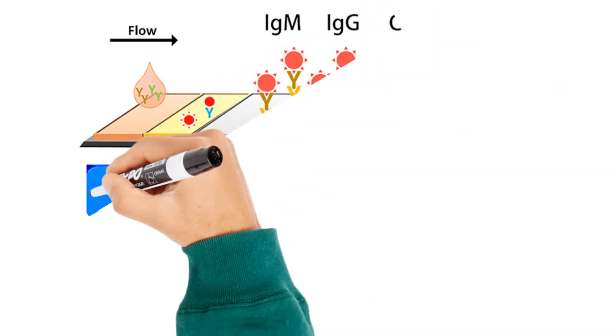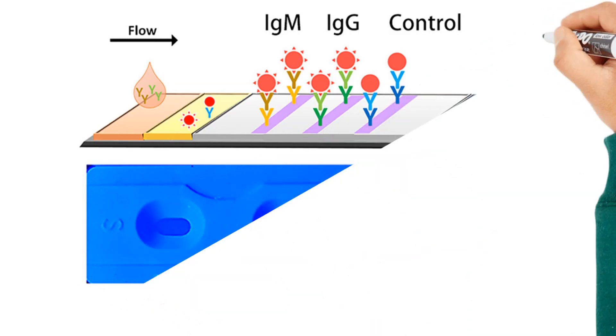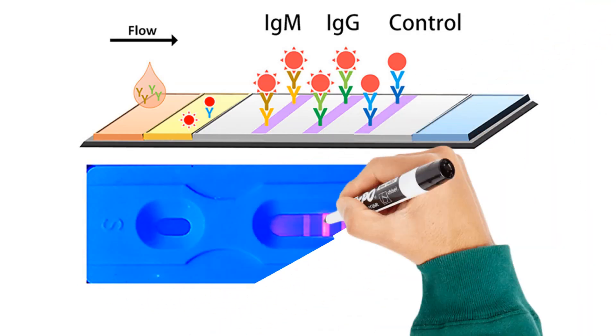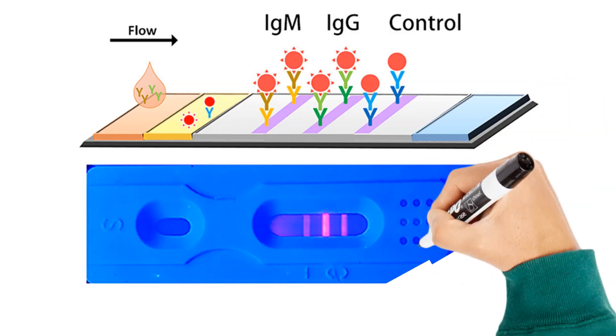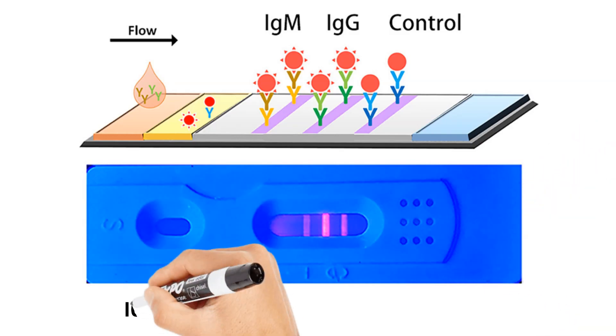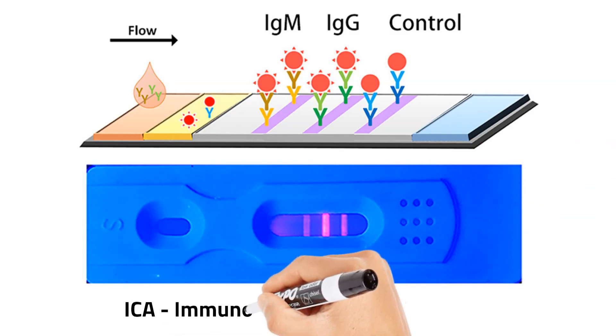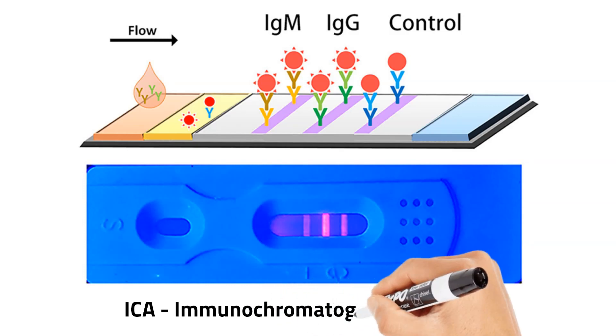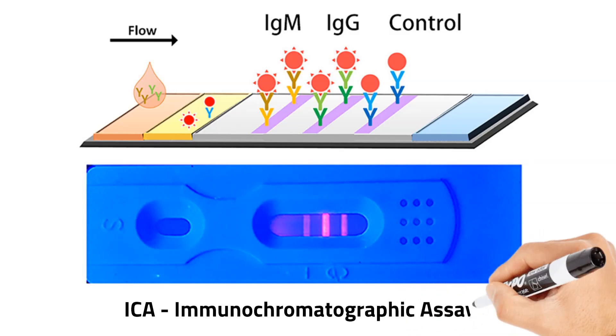Immunochromatographic assay, or ICA, also referred to as a lateral flow assay or strip test, is a simple and rapid immunoassay technique usually used in point-of-care testing. The assay consists of a porous membrane containing immobilized capture antibodies. When a sample is applied to the membrane, the target analyte, if present, binds to the capture antibody. The resulting complex then migrates along the membrane and interacts with labeled detection antibodies, generating a visible signal, such as a colored line, which is visually interpreted.